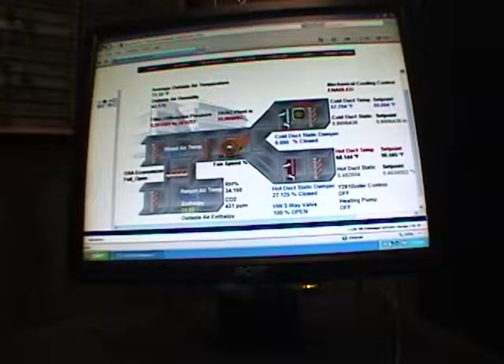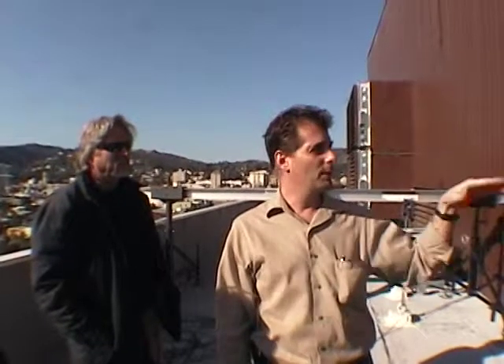If you don't know what your CO2 levels are, that's a problem by default. So Greg said let's monitor — let's put a sniffer on there and monitor what your CO2 levels are, because you can go up to like 900. We were on like three or four hundred when we closed the dampers, and since that time we've been tracking it.